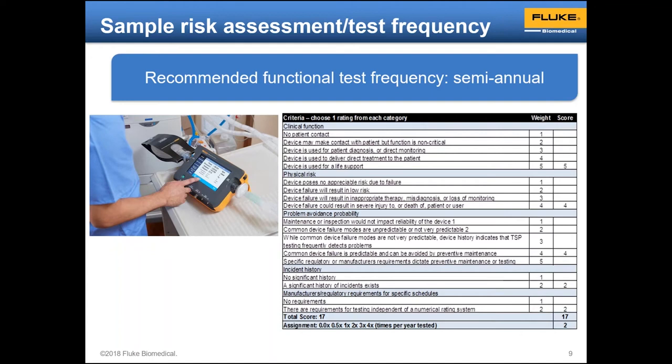You could say 365 days a year, and they are, but this past year, there has been a much bigger number of ventilators operating that much. So things happen when you operate equipment like that, and it's important that you do all of the testing. So we'll test ventilators twice per year, including the electrical safety.